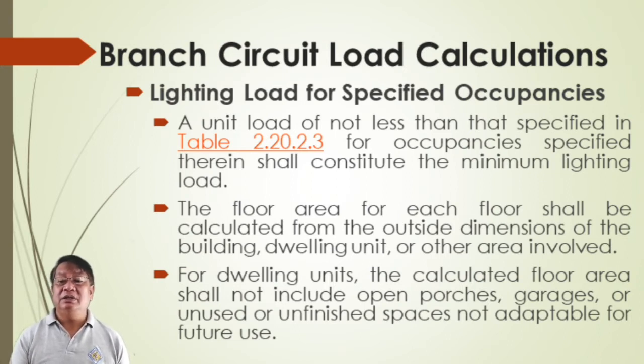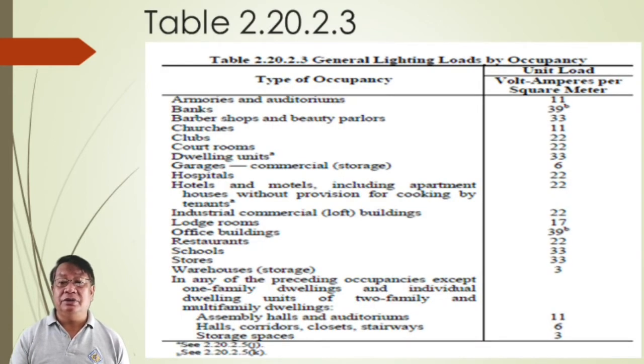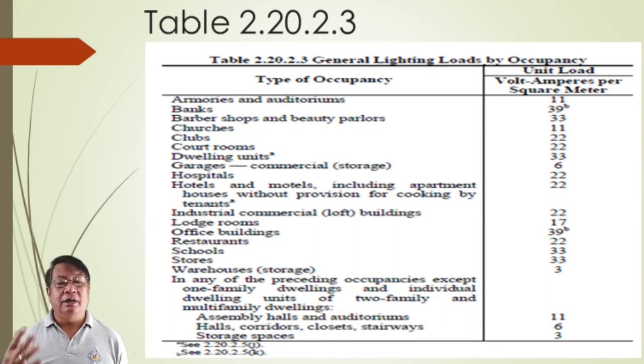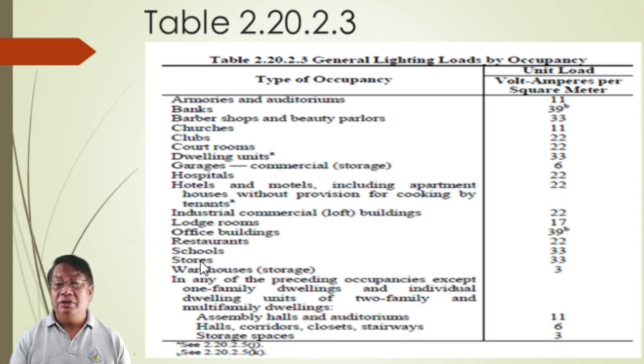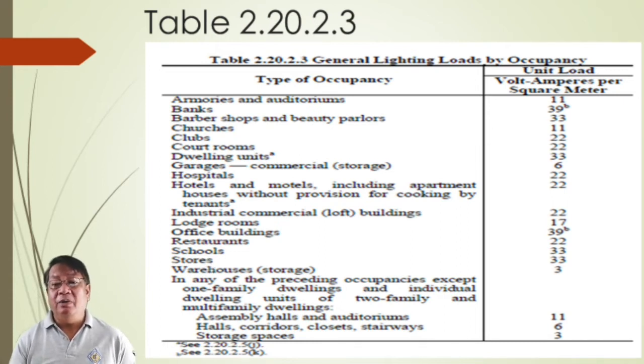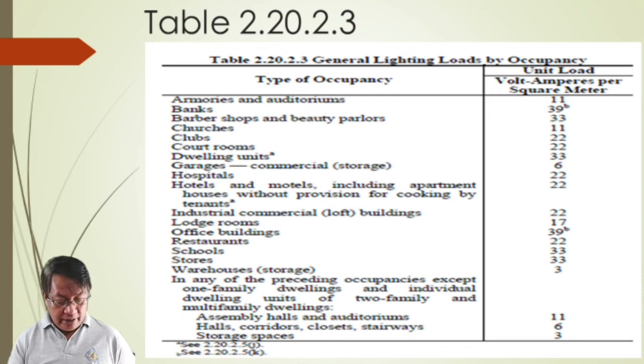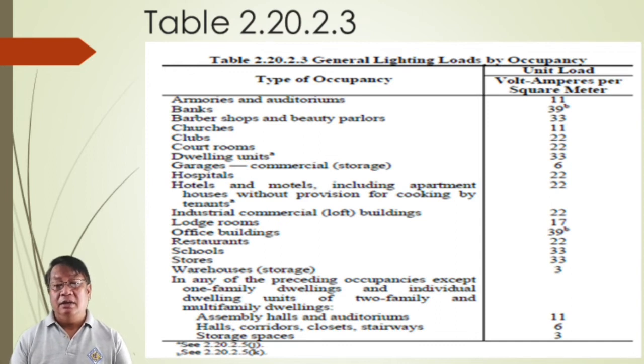This is the table for general lighting loads by occupancy, our estimation in volt-amperes per square meter. For example, for schools, the rated apparent power for classrooms is more or less 33 volt-amperes per square meter. So if we have 1,000 square meter classrooms, multiply by 33 to get 33,000 VA or 33 kVA as our power allocation for that area.